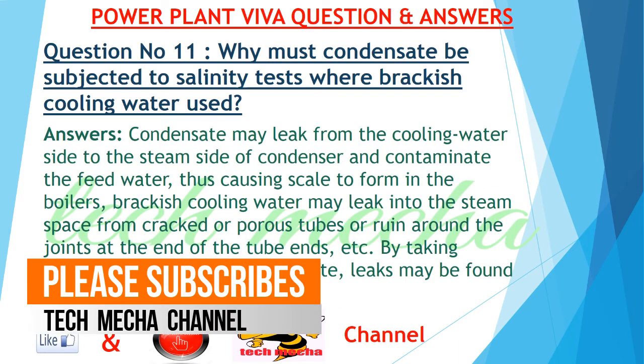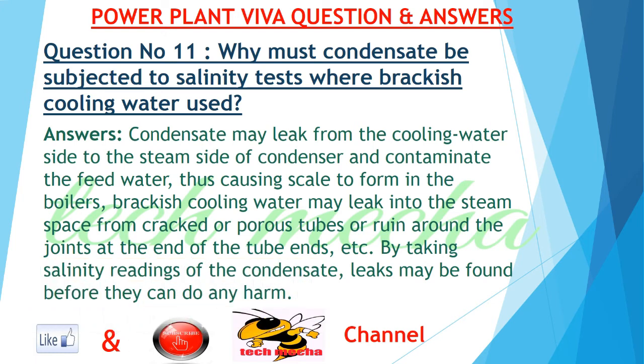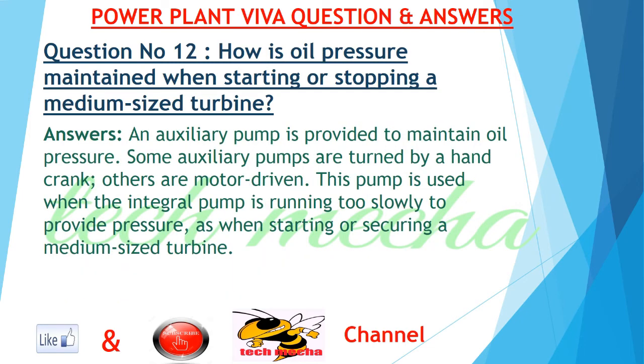Question number 11: Why must condensate be subjected to salinity tests where brackish cooling water is used? Answer: Condensate may leak from the cooling water side to the steam side of the condenser and contaminate the feed water, thus causing scale to form in the boilers. Brackish cooling water may leak into the steam space from cracked or porous tubes, or around the joints at the tube ends. By taking salinity readings of the condensate, leaks may be found before they can do any harm.